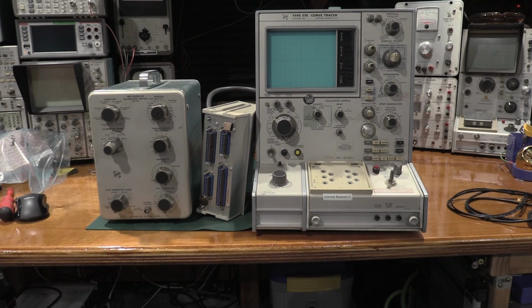If there's equipment on the bench, I want to know it's within factory specifications so I can believe what it's telling me. The specification can be quite loose. I have some meters that aren't very accurate, but they're within spec. So that's kind of what I'm looking for in equipment that I'm using personally, especially when I'm servicing equipment for other people.